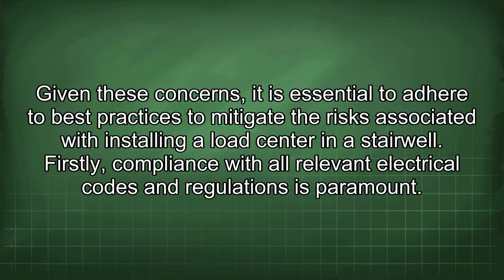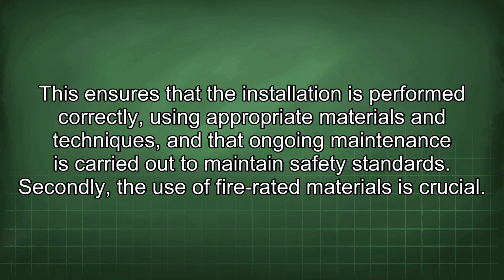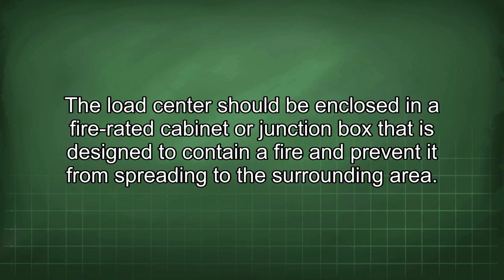Given these concerns, it is essential to adhere to best practices to mitigate the risks associated with installing a load center in a stairwell. Firstly, compliance with all relevant electrical codes and regulations is paramount. This ensures that the installation is performed correctly, using appropriate materials and techniques, and that ongoing maintenance is carried out to maintain safety standards. Secondly, the use of fire-rated materials is crucial. The load center should be enclosed in a fire-rated cabinet or junction box that is designed to contain a fire and prevent it from spreading to the surrounding area.